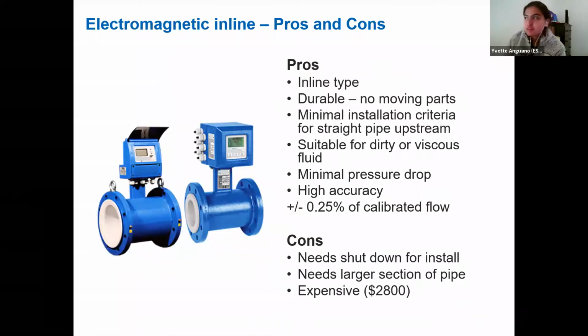And so next we have the electromagnetic inline sensor. So this is, as opposed to the insertion meters, an inline meter. These are a bit bigger, more accurate, a fancier version of the electromagnetic insertion style. There are no moving parts, they're durable and have extremely high accuracy and very minimal pressure drop. They do, however, need a larger section of pipe and can be expensive.